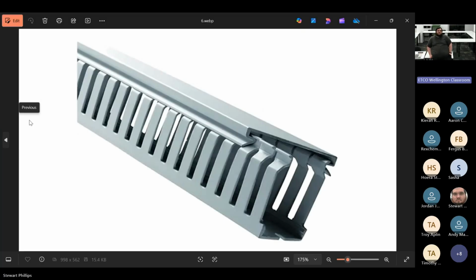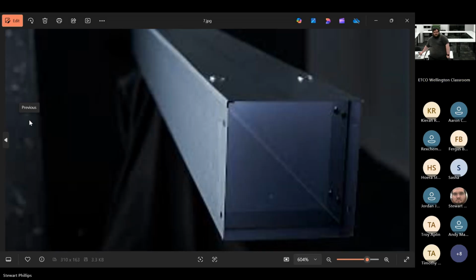Cool. So this is your capping or trunking for inside of your industrial control boards. So it's got little fingers, with gaps, so you can get the wires out to your control devices. So mostly you will see this in switchboards, sometimes in offices. And then this is your steel box trunking, or sometimes it comes in stainless steel or aluminium. And so this is what you kind of run around the edge of the office to run your PowerPoints. So if you're carrying the plastic stuff, it's not too bad. If you're carrying the heavy gauge steel stuff, it gets old real quick.